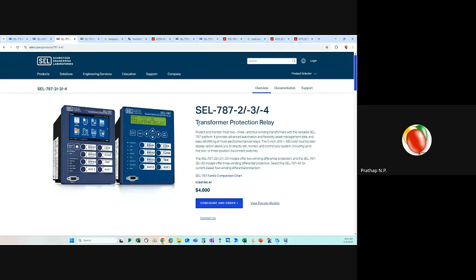What else have we got? This is the actual transformer protection relay. It has a differential. Okay, I wanted to show this one. So this was the low energy, I think LEA means low energy application, current and voltage sensor output. So you don't have to bring in an actual CT and PT control circuit from the transformer CTs to this relay. You can just have those Rogowski coils, CTs, or even nowadays we are starting to see optical CTs that can be connected. So see what all is available.